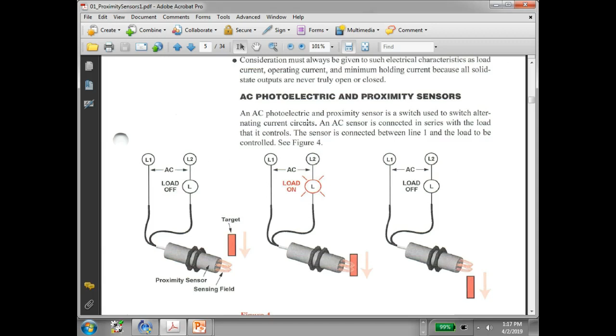So at 120 volts, we can afford to lose 4 volts and not have any problem, as long as we don't string a bunch of these things together. But in a 24 volt AC circuit, odds are your inductive sensors are going to be 3-wire sensors, because now you can't afford to lose 4 volts. So ours is going to be 2-wire sensors, because these are 120 volt inductive sensors, and these will be powered up through the load.